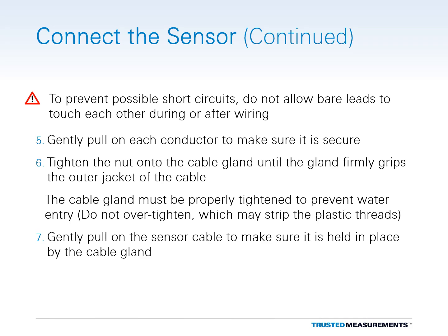Next, tighten the cable gland nut until it firmly grips the outer jacket of the cable. The cable gland nut must be properly tightened to prevent water entry. Avoid over-tightening the nut, which may damage the plastic threads of the cable gland. Lastly, gently pull on the cable to make sure that it is held in place by the cable gland.